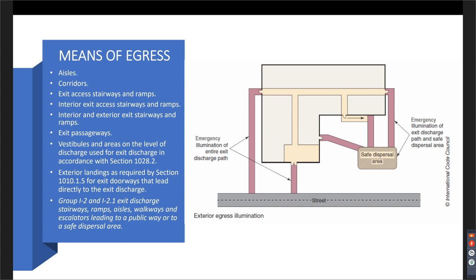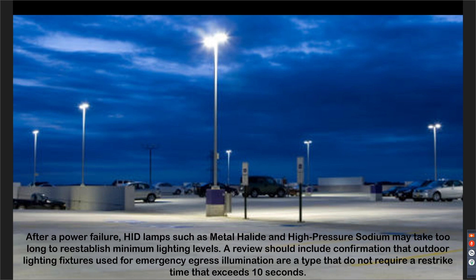I'm not going to read all of those, but maybe the most important one, the very bottom one, in I-2.1 occupancies, the exit discharge stairways, ramps, aisles, walkways leading to a public way or to a safe dispersal area also have to have emergency lighting, not just the landing. All the way through, so all the way through to the public way, the street, or if they have a safe dispersal area, through that. And keep in mind when you have different lighting out in those areas, maybe that parking area, for example, that ramps up slowly for energy purposes. Be careful with that, because that lighting is still required to be on e-power and to provide the minimum lumens within the 10 seconds. So watch the type of lighting that's provided through to that public way or safe dispersal area.